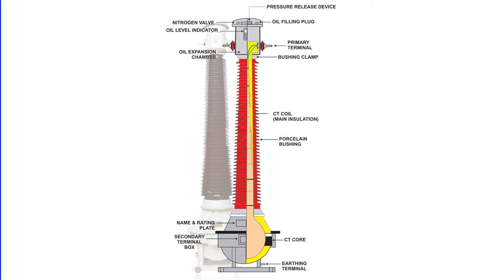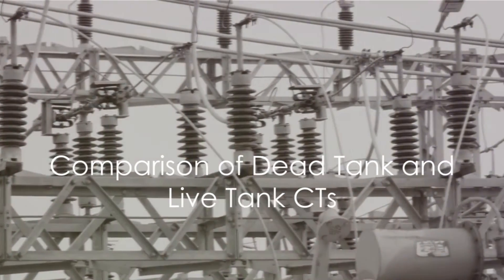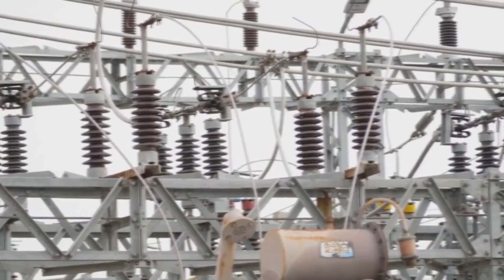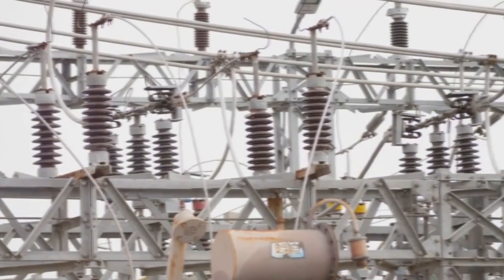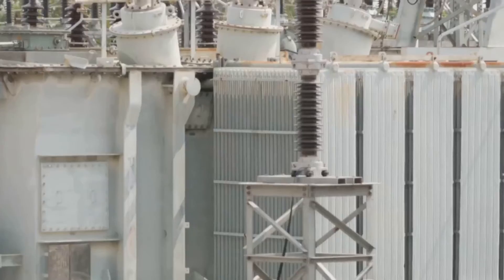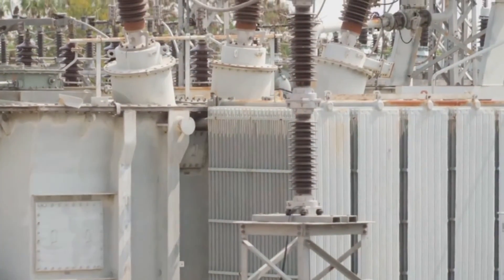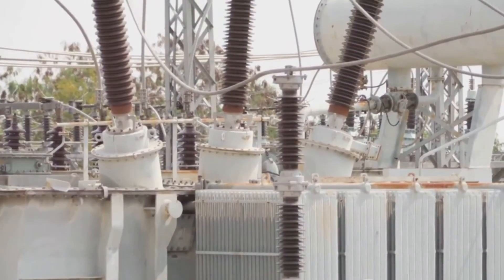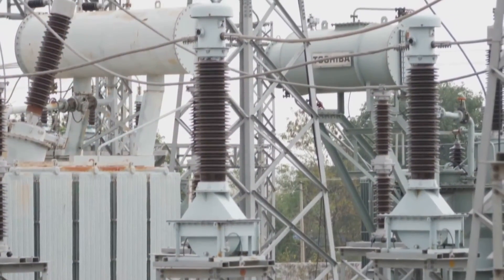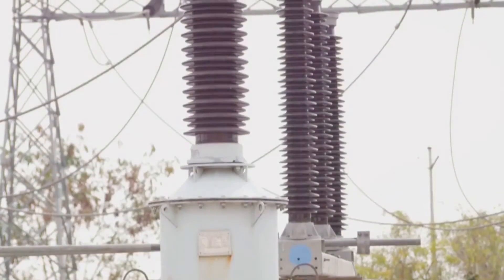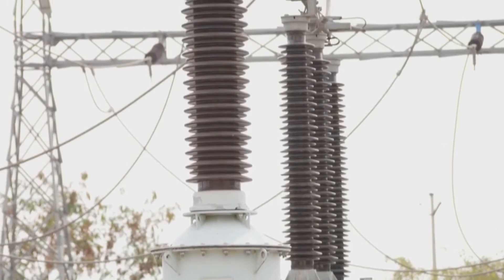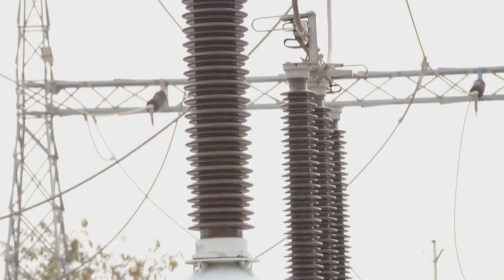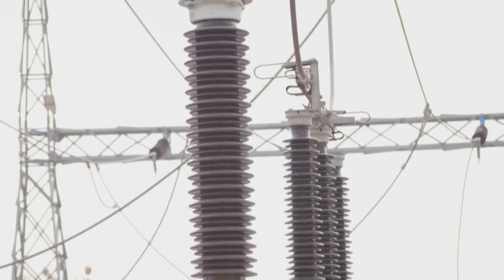Heat generation during short-time thermal current is also at its maximum in dead tank CTs. In summary, live tank CTs are compact, economical, and generate less heat due to their shorter primary winding. They're also easier to insulate and have better transient performance. On the other hand, dead tank CTs are bulkier, pricier, and generate more heat. They're also harder to insulate and potentially more prone to insulation damage due to mechanical forces.